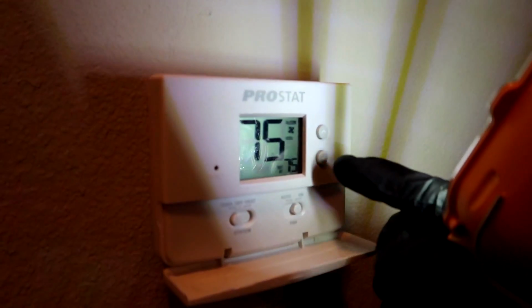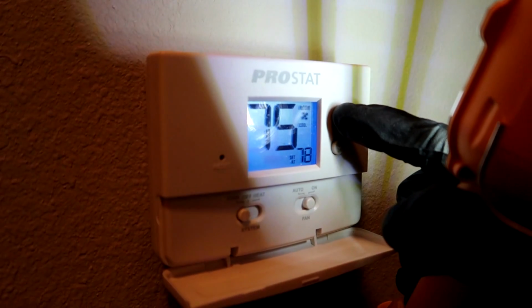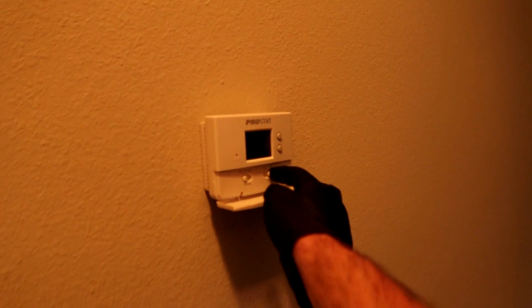Yeah, this one's frozen up as well, so it's probably going to be a leaky coil. See that ice there? We'll see. It's definitely low on refrigerant. Cut the fan on and melt the rest of that ice. Go get him a new filter. I'll be back. Alright, we should be thawed out by now. Let's go ahead and turn the fan off.